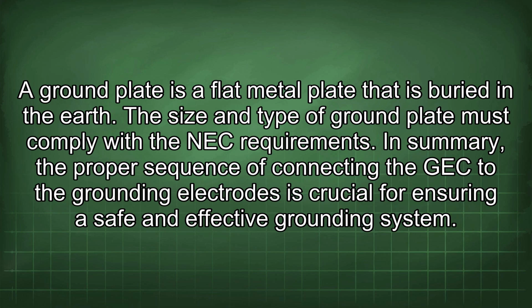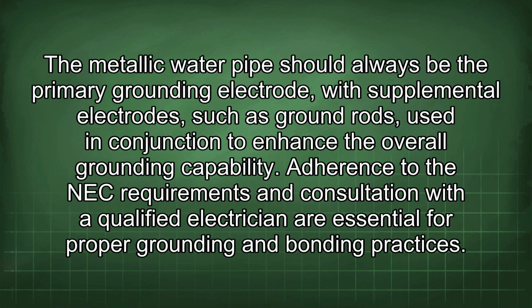In summary, the proper sequence of connecting the GEC to the grounding electrodes is crucial for ensuring a safe and effective grounding system. The metallic water pipe should always be the primary grounding electrode, with supplemental electrodes such as ground rods used in conjunction to enhance the overall grounding capability. Adherence to the NEC requirements and consultation with a qualified electrician are essential for proper grounding and bonding practices.